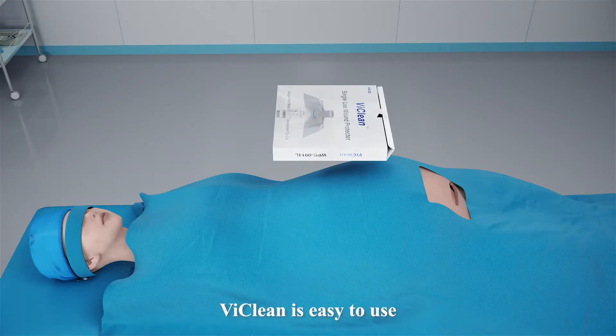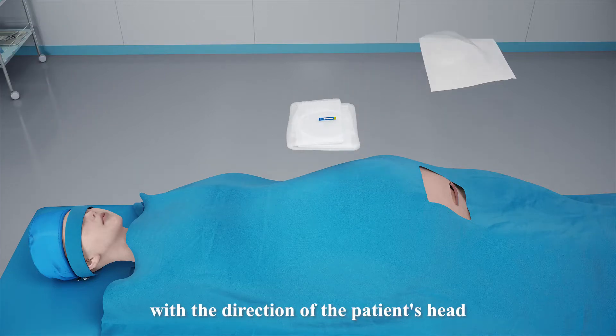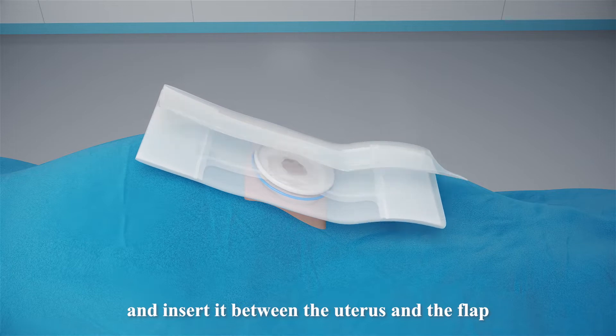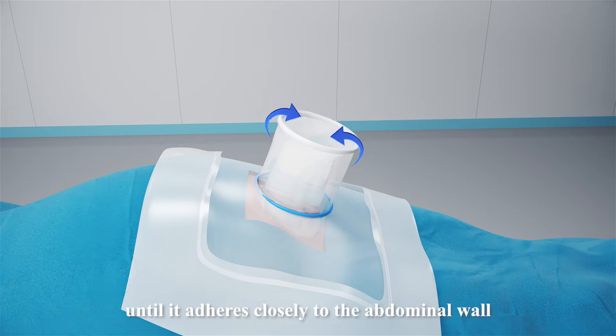ViClean is easy to use. First, open the package and align the arrow with the direction of the patient's head. Then, lower the embedding ring and insert it between the uterus and the flap. Once in place, unfold the wound protection film. Lift the outer ring and roll it down until it adheres closely to the abdominal wall.